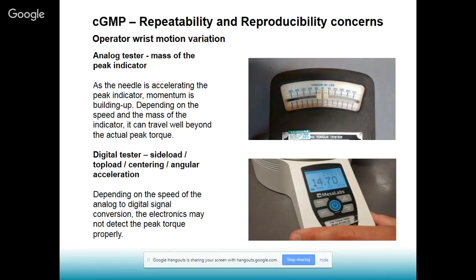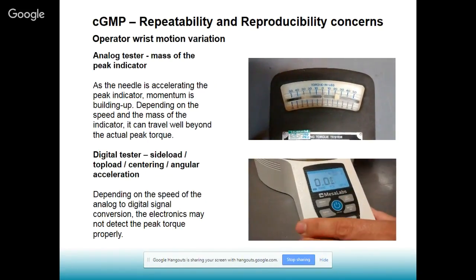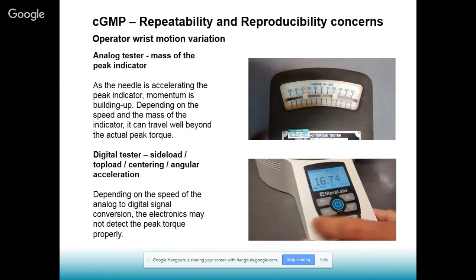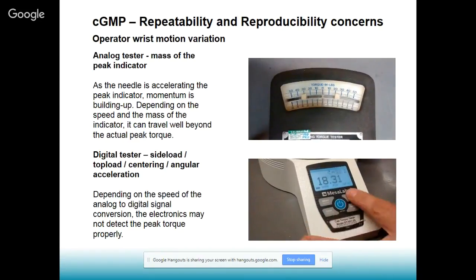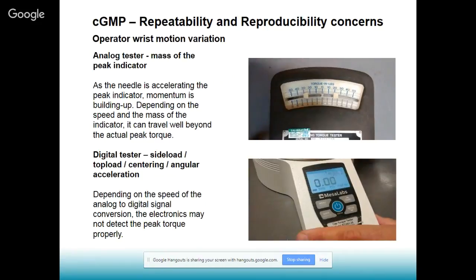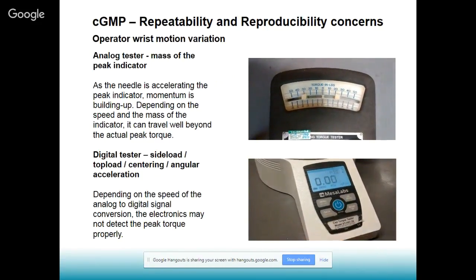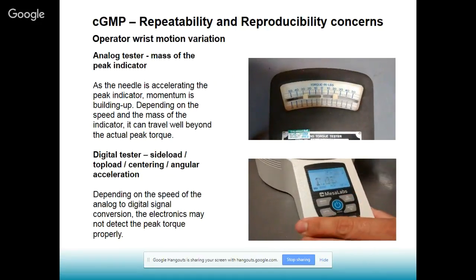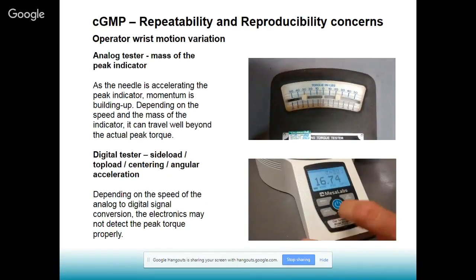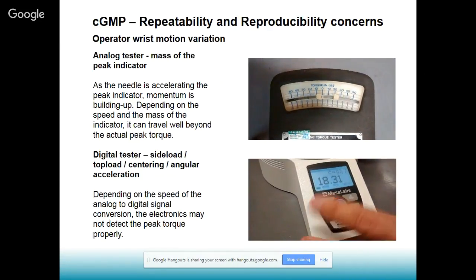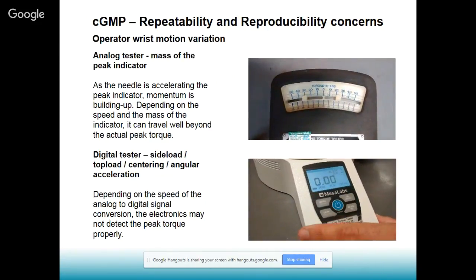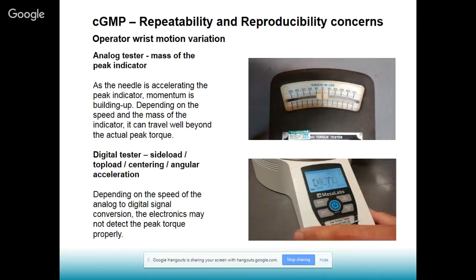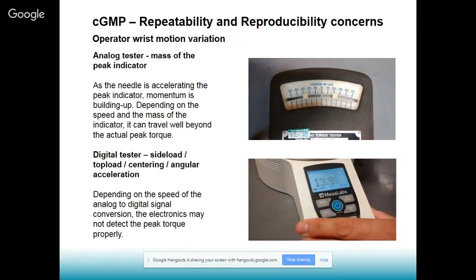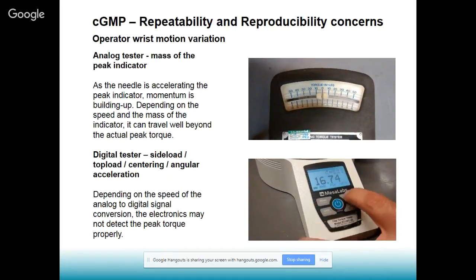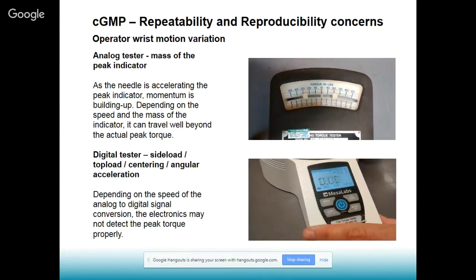And here's an example of a spring-based needle and peak indicator type torque tester, and below is a digital torque tester. These are both manual devices, and my intention here was to show that both of them can display large standard deviation for our magnetic gold bottle torque reference. That gold bottle has a very repeatable breakaway torque. But if your operators are not controlling their wrist motion, they can still get so much variation in the torque readout, because the speed of the rotation is very important when we do the torque tests.